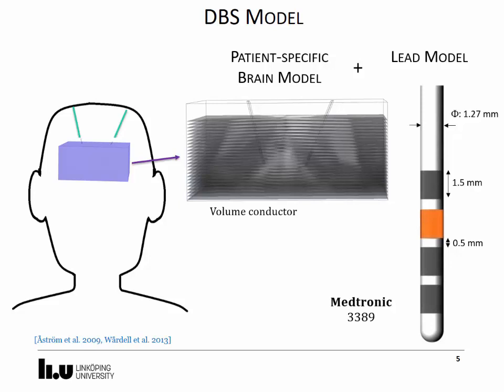As an example, here a conventional lead model 3389 manufactured by Medtronic. This lead has four platinum iridium contacts or electrodes of 1.5 mm length separated by 0.5 and 1.5 mm of insulation material, but other designs, such as directional leads, can also be used.